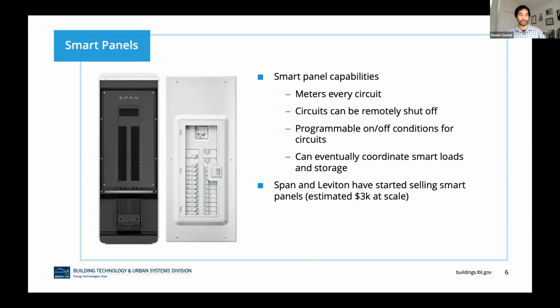For example, if I were to replace my 100 amp panel with a smart panel, I could program it to make sure that a new EV charger, a new induction range, and a new water heater are not all turned on at the same time. That way I can make sure I don't go above the 100 amp capacity of my panel or my feeder. As mentioned, you do need to do a panel upgrade.